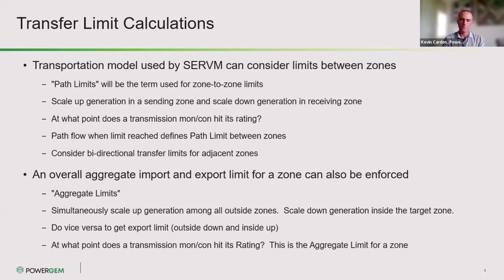So if between zone A and zone B we could scale up generation by 4,000 megawatts in one zone and scale down by 4,000 megawatts in another, we have a net flow of 4,000 megawatts across that path - that determines our transfer limit. We also do an aggregated transfer calculation where we scale up generation in one zone and scale down in all other zones, which tells us our export limit. Then the same idea but scaling down in the receiving zone and scaling up in the external world, to see how much we can change before hitting those transfer limits.